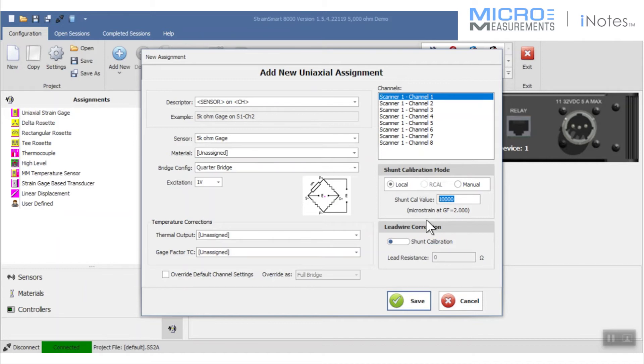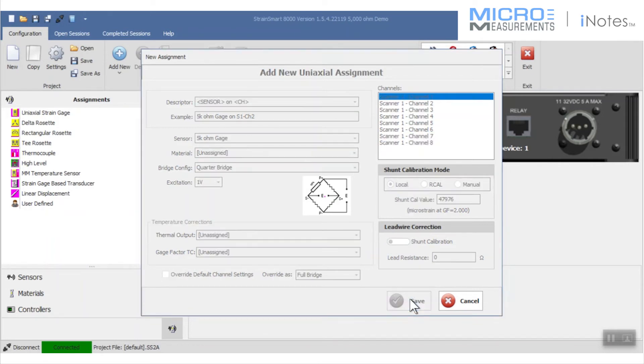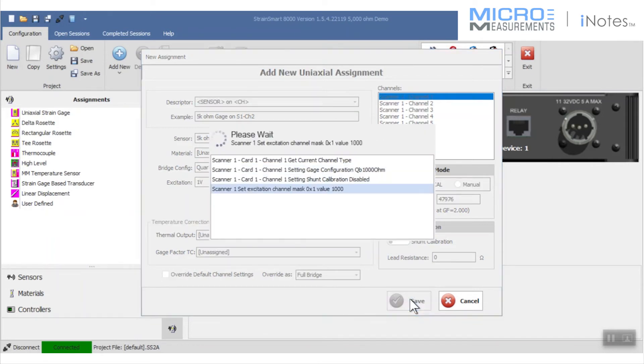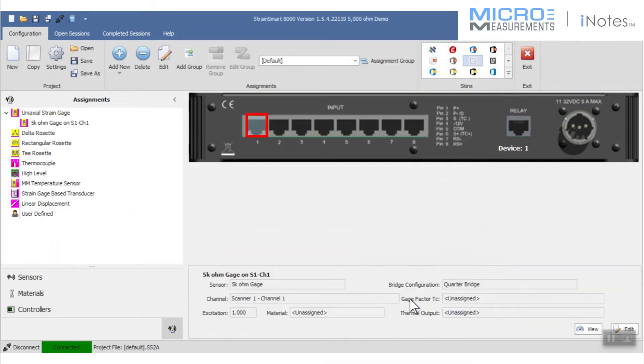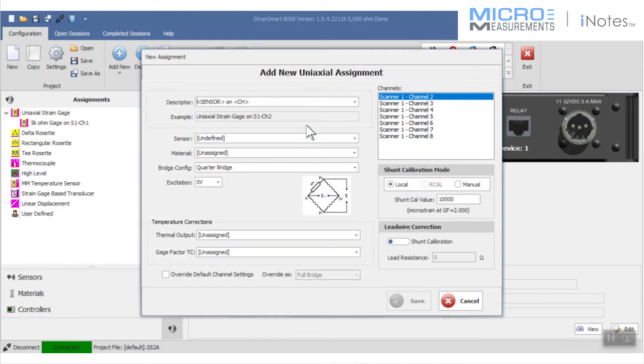Now what I need to do is tell it that after calculating, that same shunt cal resistor value is going to generate a strain of about 47,976 when it's on a 5,000 ohm dummy. I'm still shunting the dummy because I want to take care of any lead wire resistance. What I'm going to learn very quickly is that with the 5,000 ohm strain gauge, the effects of the lead wire resistance really go away, even if there's a significant amount.